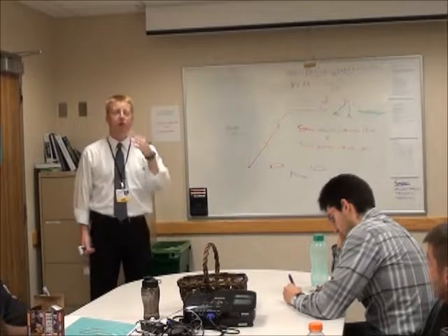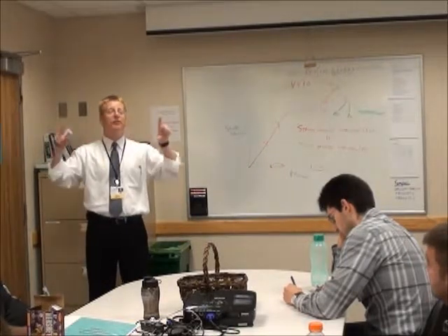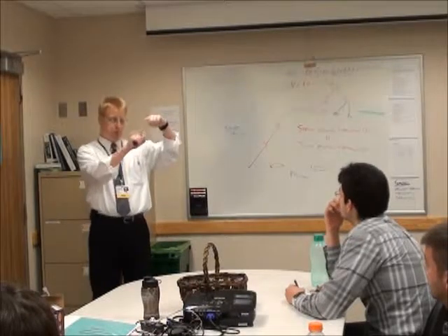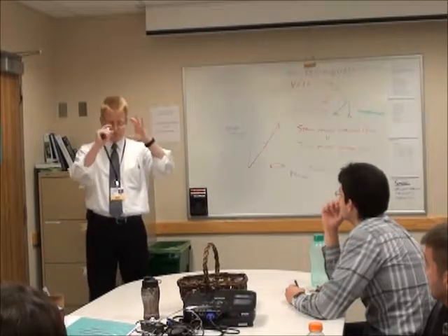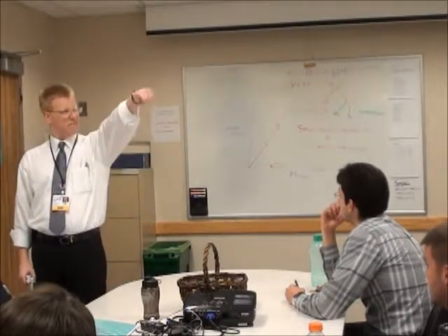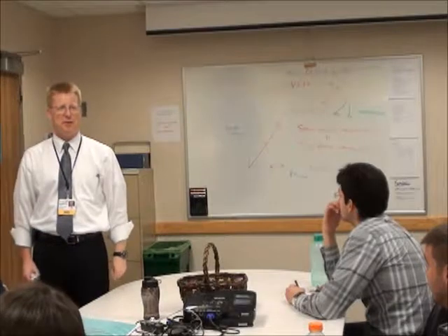Now, if you want to be a purist, you should print out that strip, measure the narrowest pulse pressure, measure the biggest pulse pressure, and see if there's a 13% difference between those two. About 13% is how I do it.